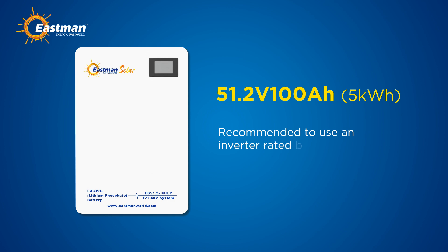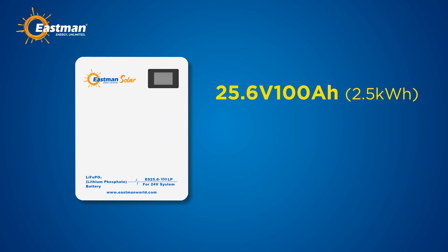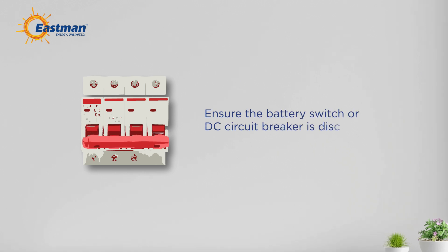When using only a 51.2 volt 100 Ah battery pack, it's recommended to use an inverter rated below 5 kilowatt. For a single 25.6 volt 100 Ah battery pack, use an inverter rated below 2.5 kilowatt. Exceeding these limits may lead to operational issues.